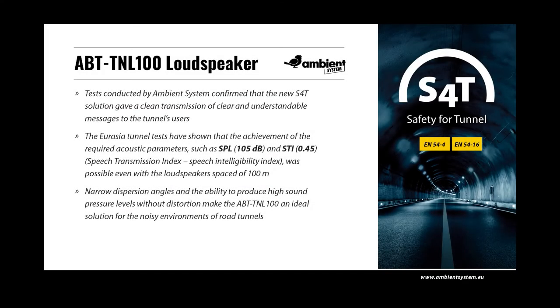ABT TNL100 loudspeakers were fully tested in the transcontinental Eurasia tunnel, measuring over 5 km in length in Istanbul, Turkey. Tests conducted by Ambient System confirmed that the S4T solution gave a clear transmission of understandable messages to the tunnel's users. Narrow dispersion angles and the ability to produce high sound pressure levels without distortion make the ABT TNL100 an ideal solution for the noisy environments of road tunnels. The tests showed that achieving a sound pressure level of 105 decibels and an STI of 0.45 is possible even with loudspeakers spaced at 100-metre distances.